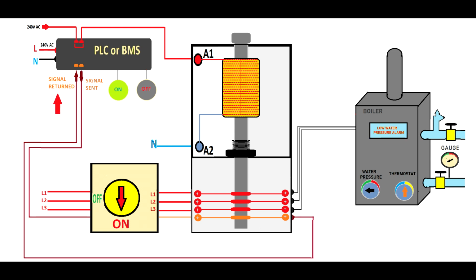I only found this type of poor integration a couple of times, and from my own perspective, this is pretty dangerous because this boiler can run without ventilation, and that can put people's lives in danger. And also the boiler can be forced to run without the heating agent pump running or without the pressurization unit, because as I said, the power circuit will be interrupted because of one of these items malfunctioning, like the pump or pressurization unit or the fan. Then the technician who is remotely monitoring the system will not be aware, because this poor integration will not send any input to his front end panel, and the technician will believe that everything is okay.